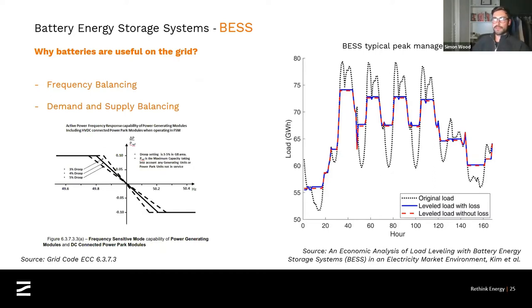Over the last 4 or 5 years, since battery storage systems have been connecting into the grid, providing frequency services has been probably the most widely used and delivered service for a battery application. As I mentioned earlier, that involves a system tracking grid frequency and responding accordingly by either exporting or importing power. The reason it does that is to try and maintain that 50 hertz level on the network. There are other applications that we can start using now, and it's really about maximizing what we can do with the inverter technology. That's what Mike's going to go on to explain in a little more detail.